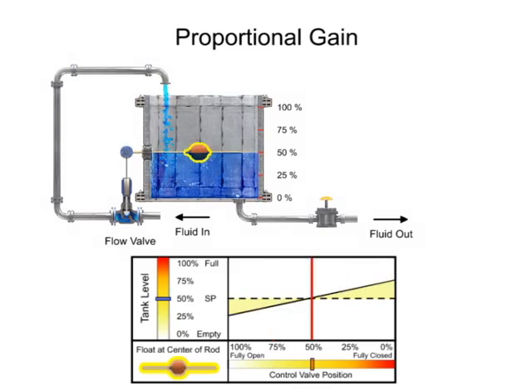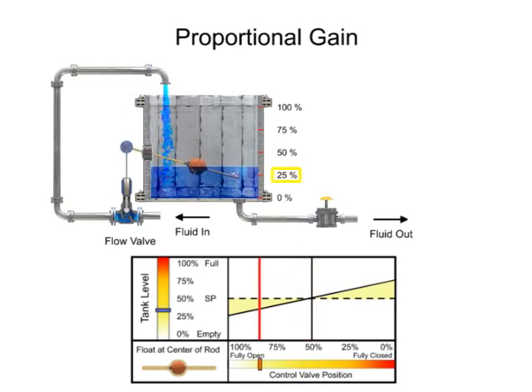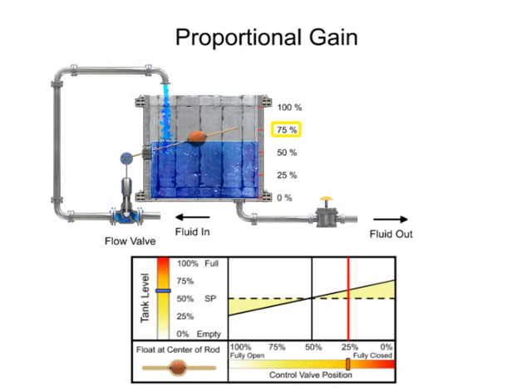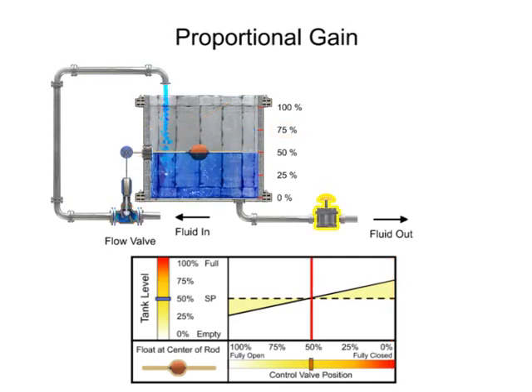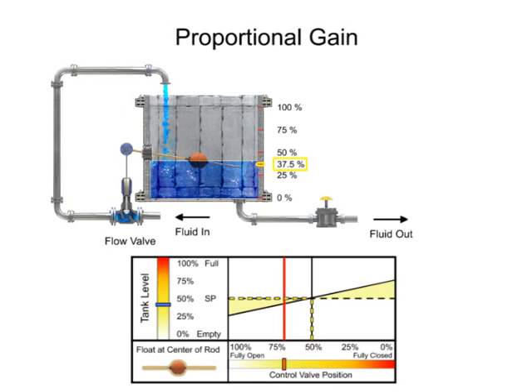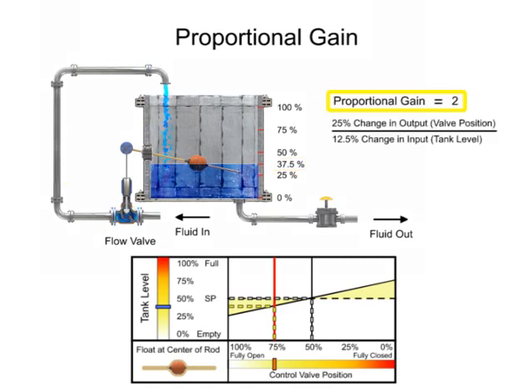Positioning the float to the midpoint of the bar increases the gain. The valve fully opens when the level drops to 25% and fully closes when the level rises to 75%. Opening the drain valve increases the load demand, which causes the tank level to drop by 12.5%, or to 37.5% full. The float drops and the valve opens 25%, which allows more fluid flow to enter the tank. A gain of 2 is demonstrated, since the 12.5% change of tank level resulted in a 25% change of valve position.